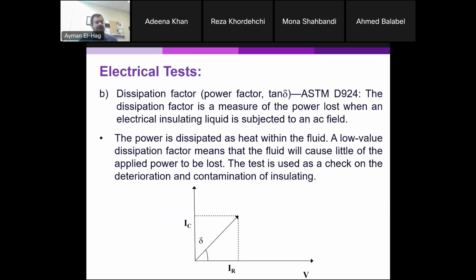Dissipation factor we talked about. And we said that the dissipation factor is a measure of the resistive part of the leakage current. If we have a pure capacitor, a pure dielectric material, it is a pure capacitive current. So there's a 90-degree phase shift between the voltage and the current. However, we have a small resistive part. Why? Now we understand, because the oil ages with time, and there are some contaminants, some polar and non-polar contaminations, exudations, fibers. There are many things there which will lead to having some definite resistive current. Small, yes, but it's still there, and we can measure it.